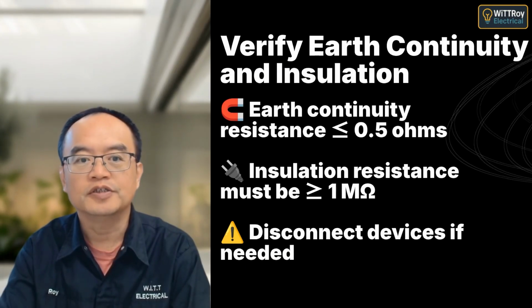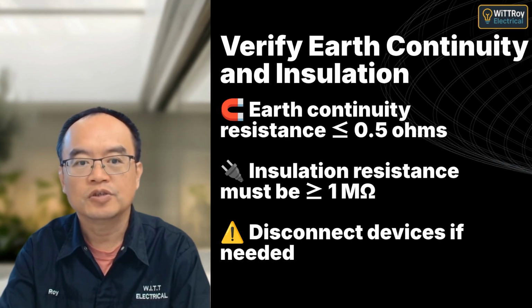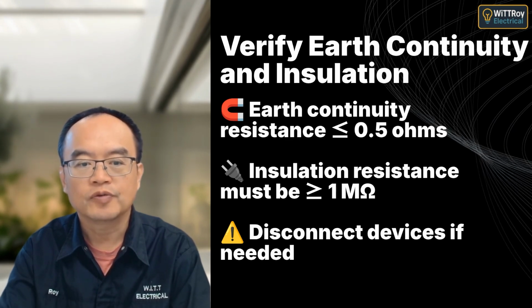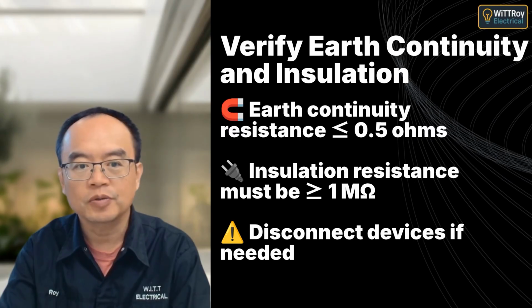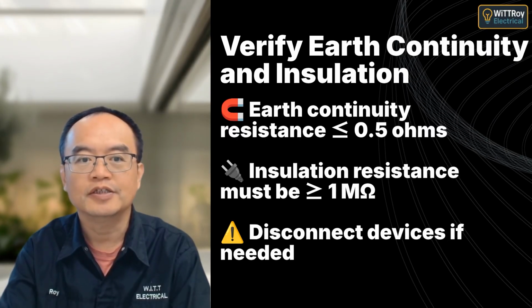Use a continuity tester to confirm the main earthing conductor has low resistance. Then test insulation with 500 volts DC. The result must be at least 1 megaohm between conductors and earth.